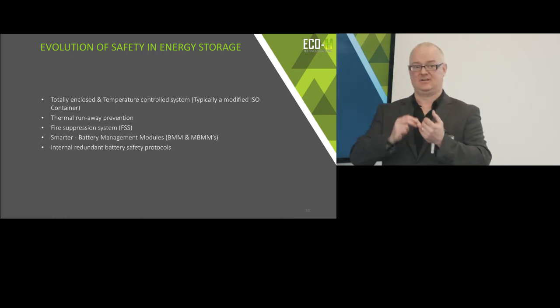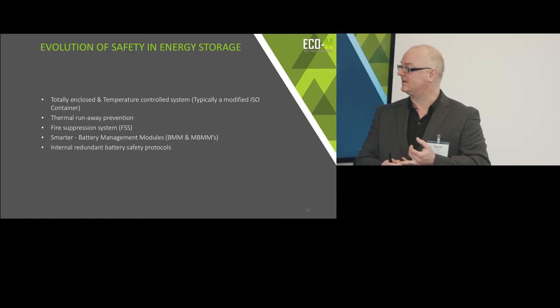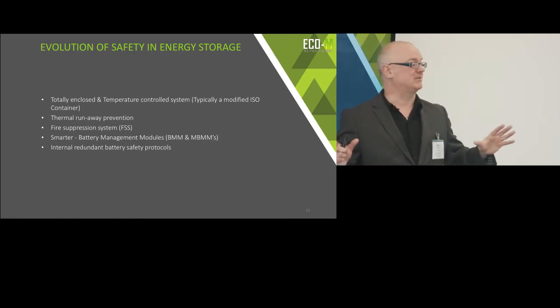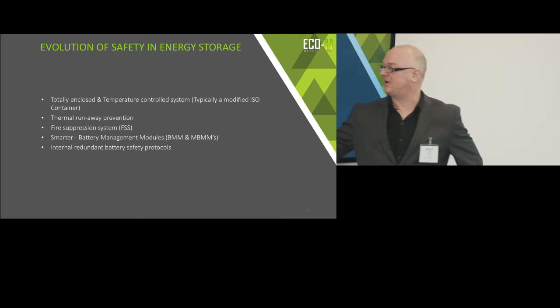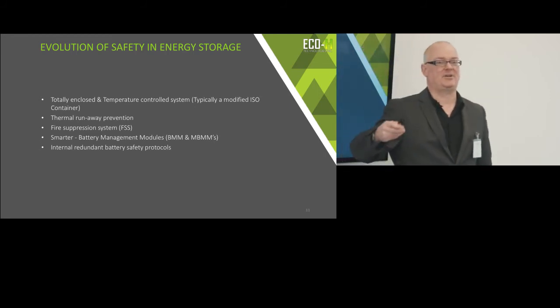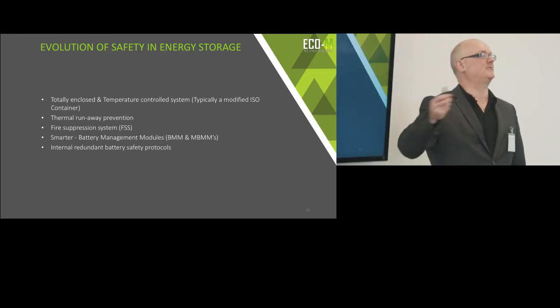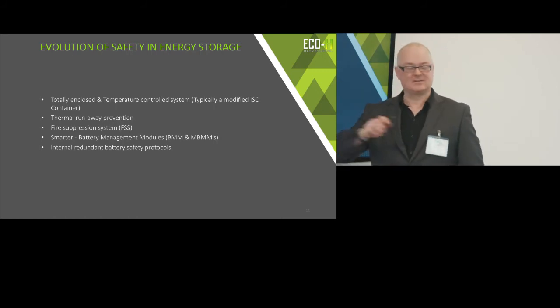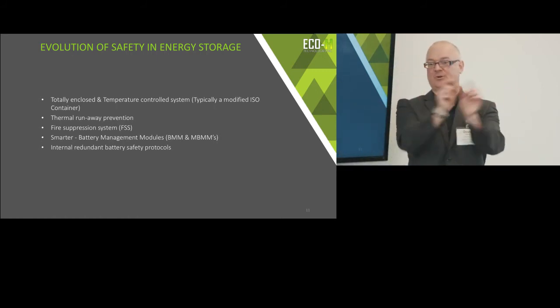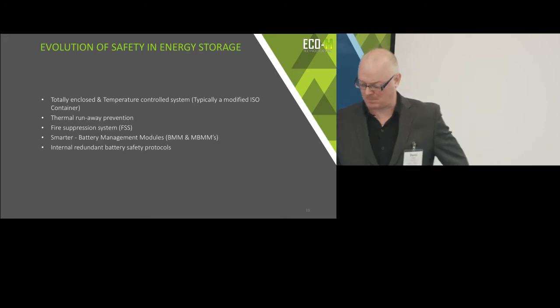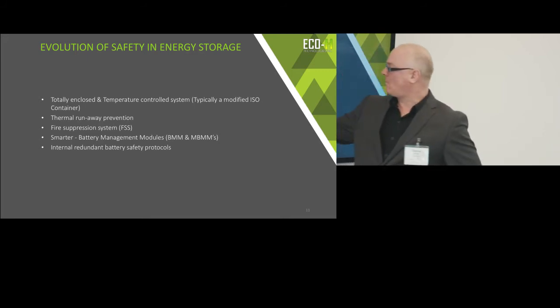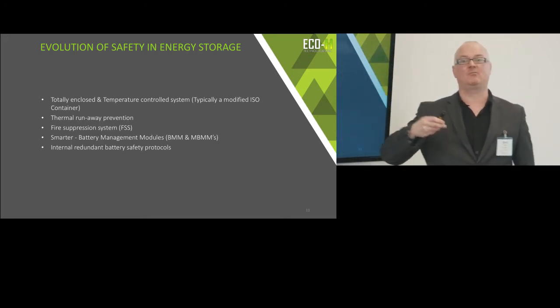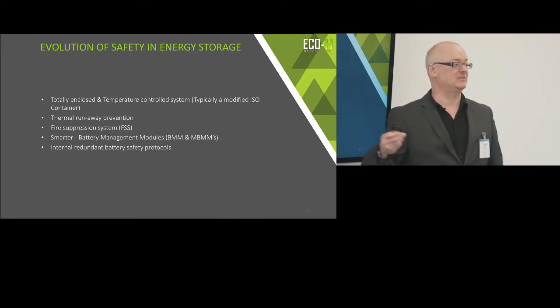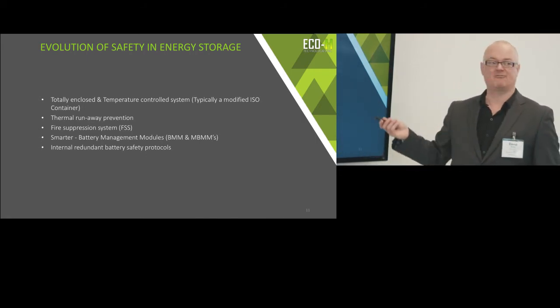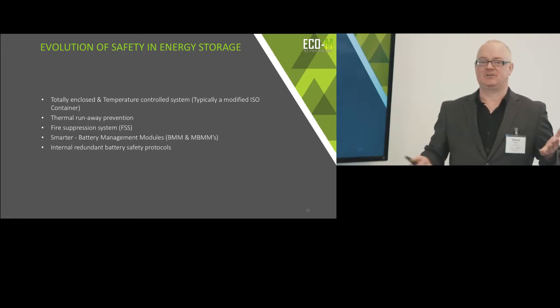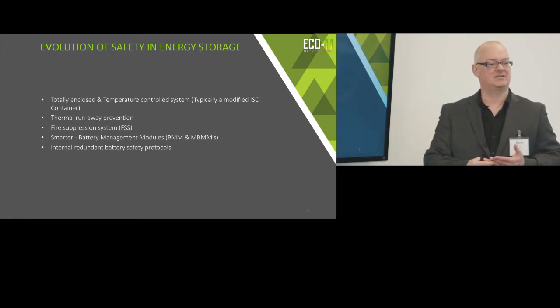So you've got a big steel box with a fire suppression system inside, and that's not even including the battery management systems. These are terms you'll hear: BMS, battery management system; MBMM, master battery manager; BMM, battery manager — anything with B and M refers to a battery manager. Each comes from a different manufacturer with different ways of preventing fires and thermal runaway. Then there's standard circuit protection too, your thermal fuses and circuit breakers.